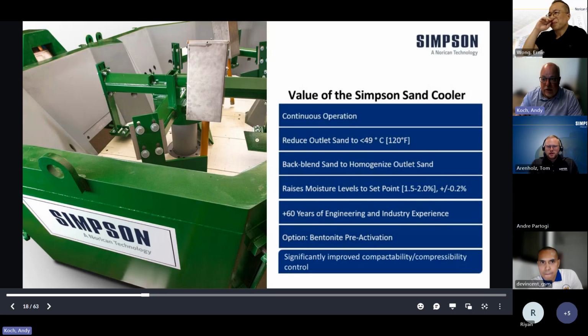But the key thing here is this isn't batch. It's continuous. So the specific customer that we're dealing with only has 8 minutes of runtime, and we recommend a minimum of 30 minutes of runtime. You can't calibrate. You can't get decent readings. You're not taking full advantage of what the multi-cooler is designed to do.